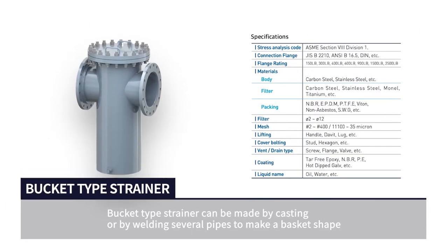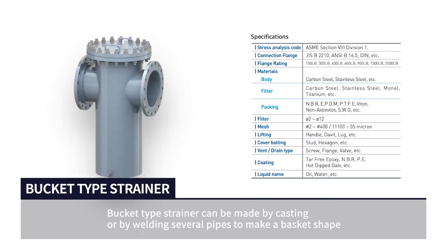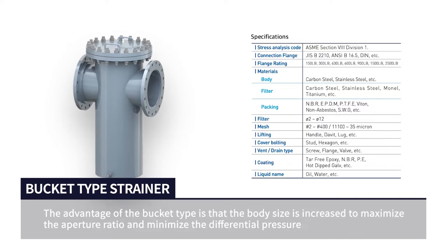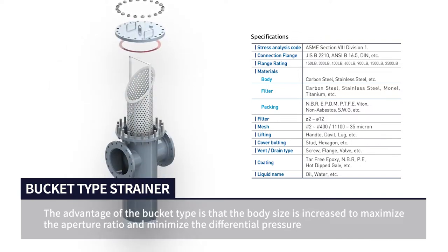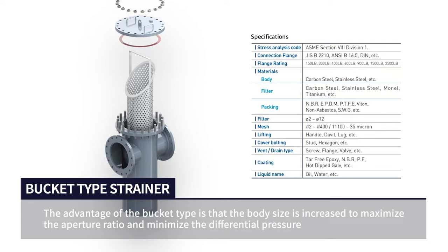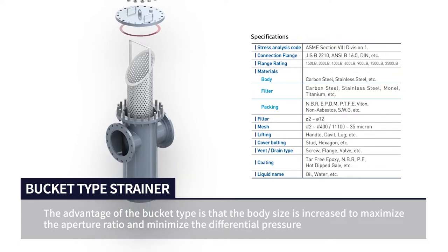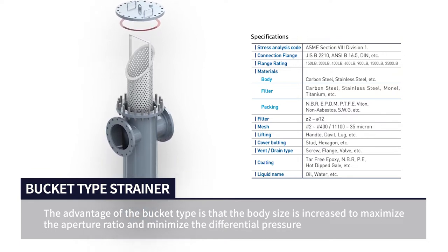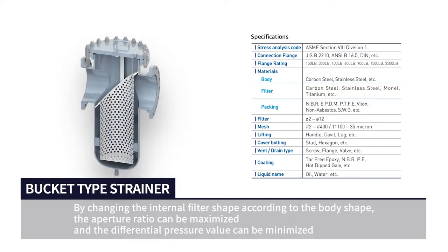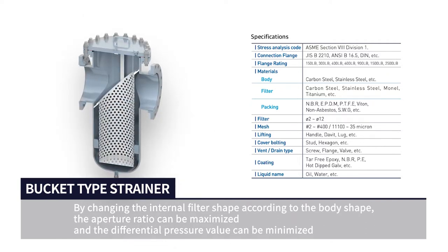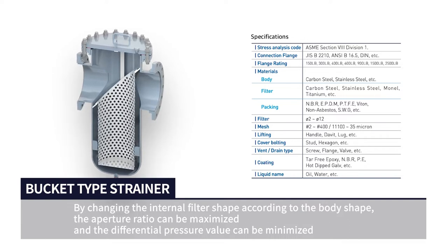Bucket type strainer can be made by casting or by welding several pipes to make a basket shape. The advantage of the bucket type is that the body size is increased to maximize the aperture ratio and minimize the differential pressure. By changing the internal filter shape according to the body shape, the aperture ratio can be maximized and the differential pressure value can be minimized.